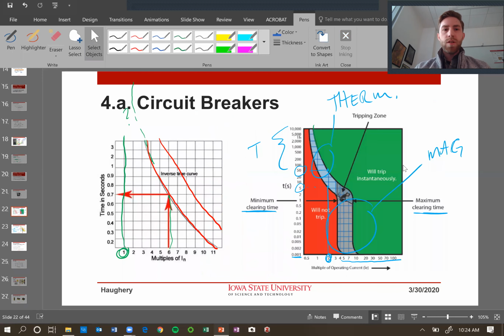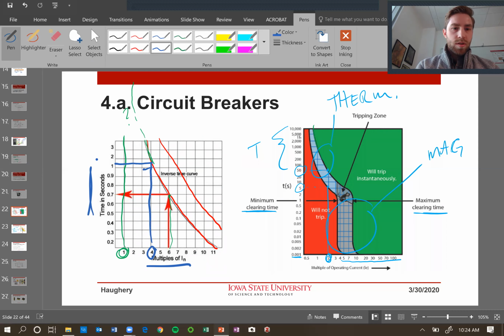We then looked at circuit breaker trip curves, and really what we're looking at here is, along our x-axis, the multiples of current: 1 times, 2 times, 3 times. And then we have our time, how long it takes for that circuit breaker to trip based on how much current multiple is flowing through the circuit breaker. So if I have a 10 amp circuit breaker and I have 4 times that, so 40 amps, that's going to take almost 1.5 seconds to trip. That's the concept of how we interpret those graphs.